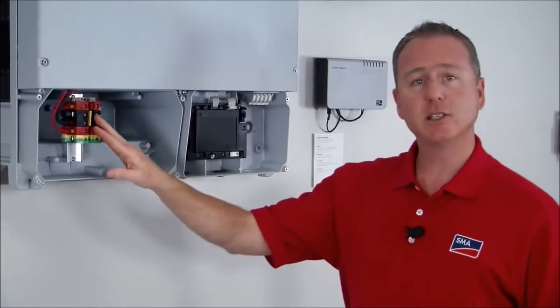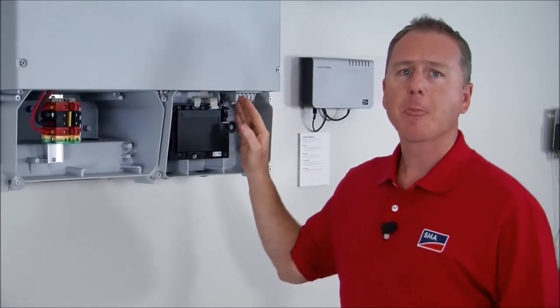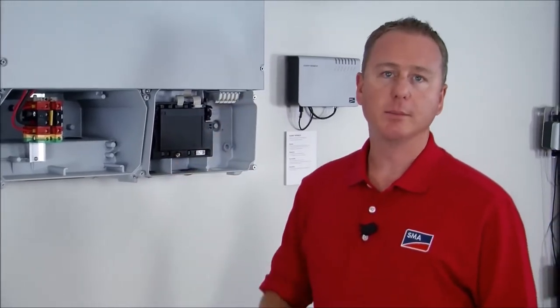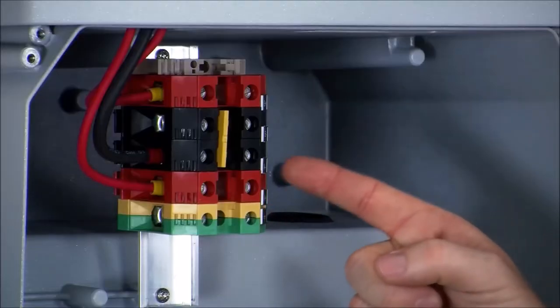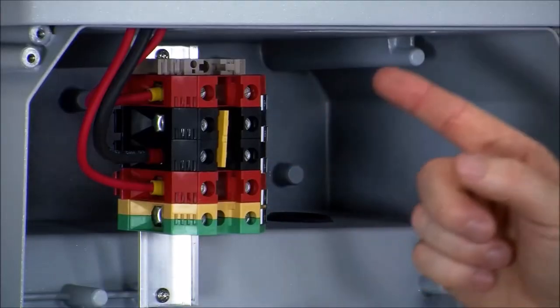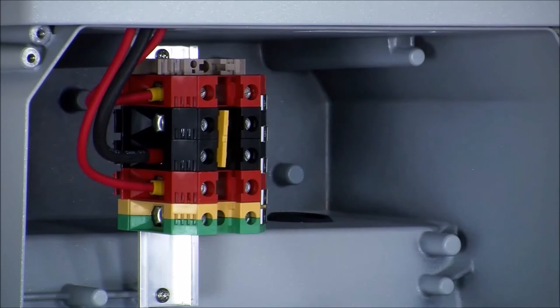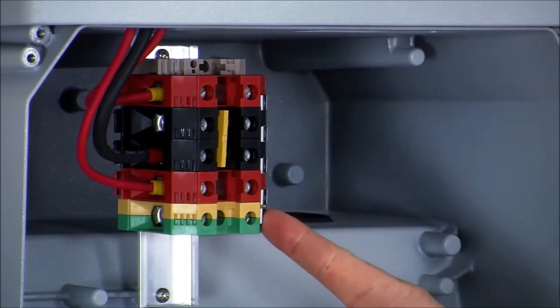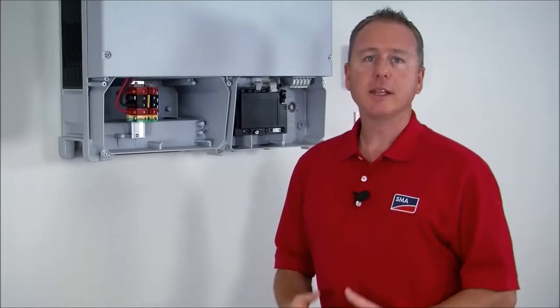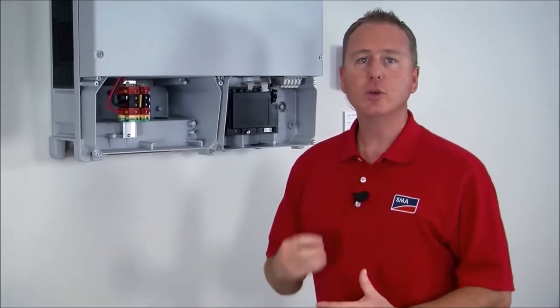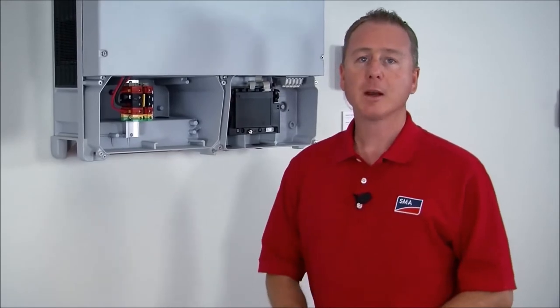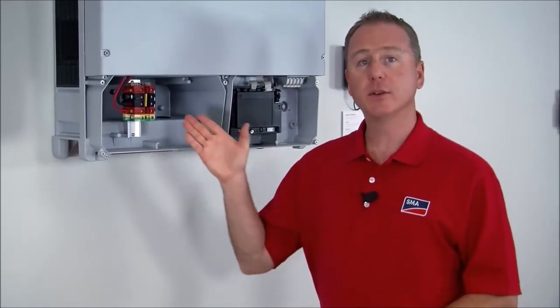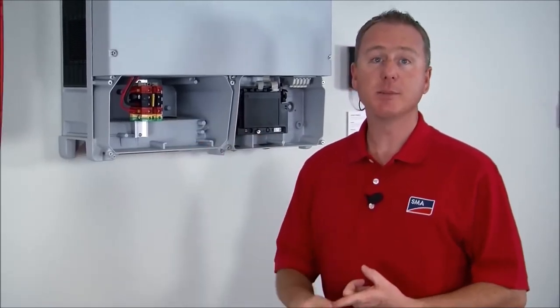There's a little bit of a difference between them. The DC terminals inside the tri-power are labeled A positive, A negative, B positive and B negative and at the very bottom is the spot where you will land the equipment ground. Now these terminals are labeled that way because there are two MPPT inputs going into this inverter. So regardless of whether you bring the conductors in from the SMA connection unit or your own combiner box or even third-party connectors, they will terminate on this terminal.